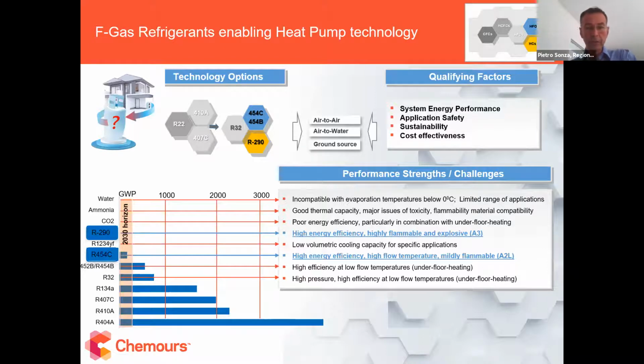So over the years, from this selection process, one midterm solution, R32, and two long-term, zero-ODP and very low GWP technologies emerged: one being R454C, or Opteon XL20, which is a hydrofluoroolefin blend, and one hydrocarbon, R290 or propane. Among the criteria and trends leading to this selection were energy performance, safety, and also ease of maintenance and installation, which is a key parameter for this technology to be broadly adopted, safely installed, and practically succeed on the market.